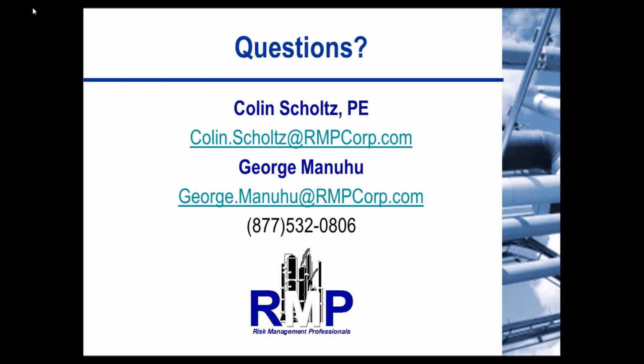Okay. Do you want to summarize? Yeah, go ahead and summarize. So one of the attendees commented back on the API issue that since OSHA PSM does not spell out what codes and standards you must follow, they only reference recognizing good engineering practices, or RAGAGEP if you prefer to say it that way. So the employer, or the owner-operator, is bound to whatever they say that they're going to follow. So they could say that they follow API standards, and then if in an audit it comes up that they're not actually following it, but they say they are, then that's an issue. However, it's typically not recommended because, as we mentioned, API is more for the oil and gas and petroleum industries and tends to be a lot more stringent than IIAR.